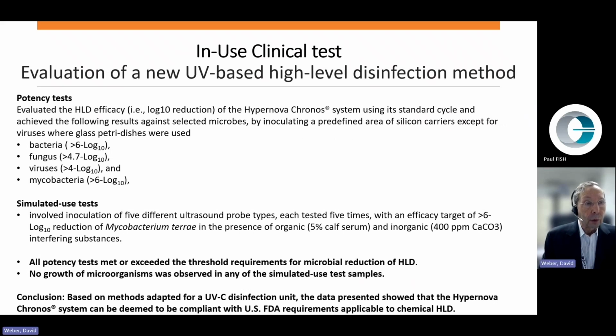So evaluation of a new UVC-based high-level disinfection method revealed the following. We'll start with potency tests. Evaluated HLD efficacy, that is log 10 reduction, using the Hypernova Chronos system, using its standard cycle, and achieved the following results against selected microbes by inoculating a predefined area of silicon carriers, except for viruses where glass Petri dishes were used. Bacteria, greater than 6 log reduction. Fungus, greater than 4.7 log reduction. Viruses, greater than 4 log reduction. And mycobacteria, greater than 6 log reduction. Now let's turn to simulated use tests.